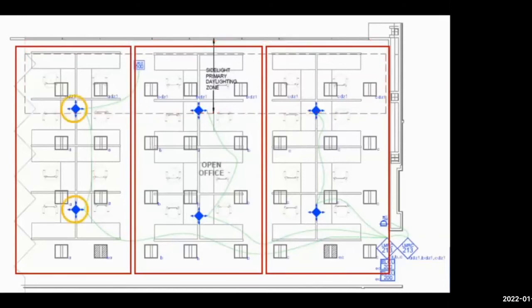On this drawing, you can also see the occupancy sensors typical for one zone, and their placement. The light level sensor detection for the daylighting. A manual switch on the wall at the entrance to the space that can be used to set the light level or turn the lights on and off manually. All of the switches and sensors come back to the central controllers here that are handling all of the control inside the space.